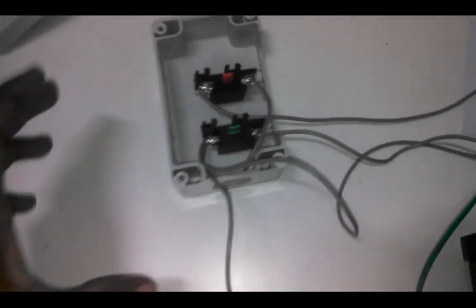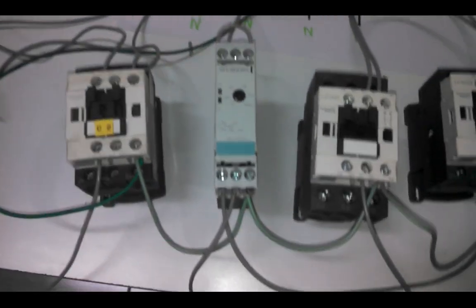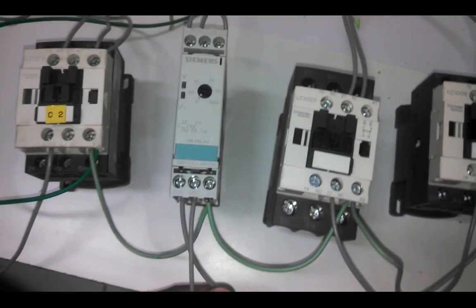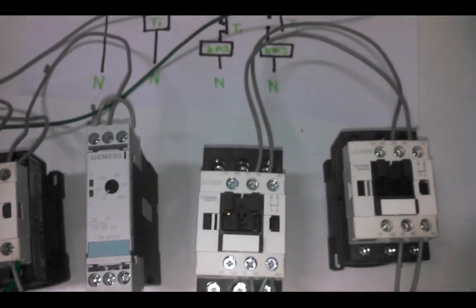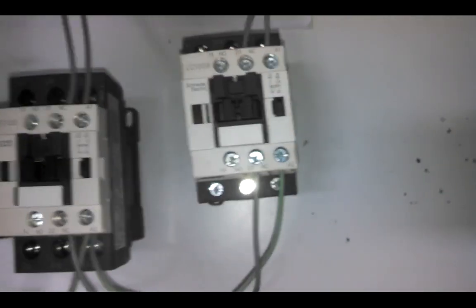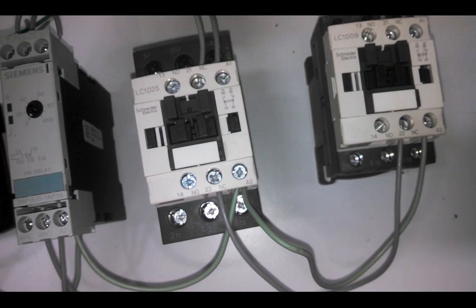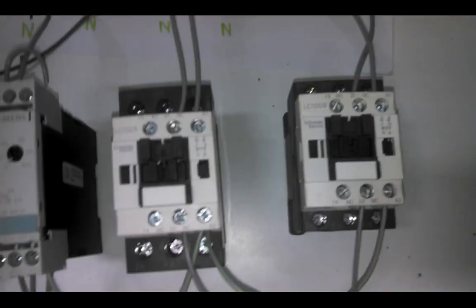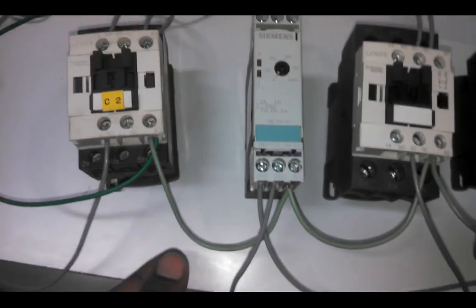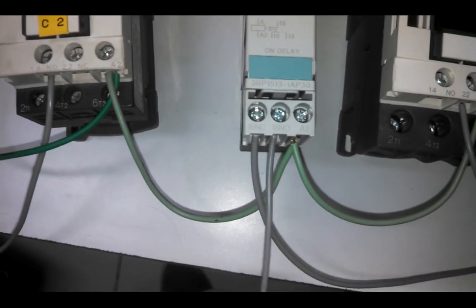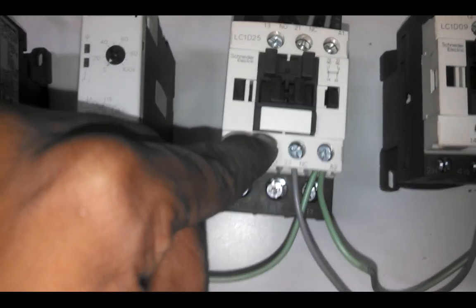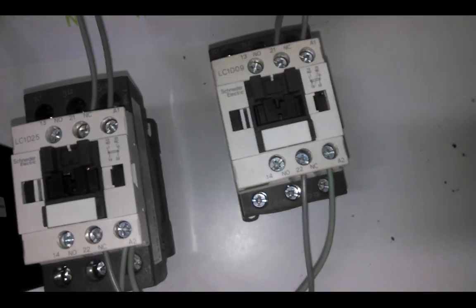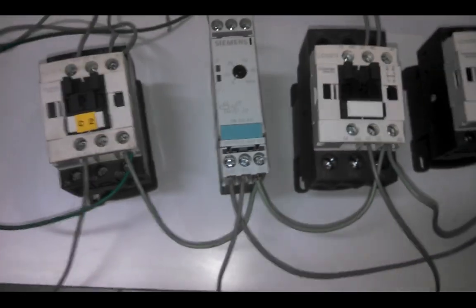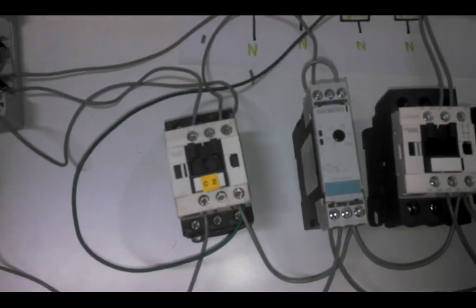So the wiring has now been done. As you can see, this portion will be our DOL starter, and then here comes the wiring for the star delta starter. The 16th terminal will pass through this NC contact, and then this came on the coil supply of this star contactor. Green is taken as neutral in the whole circuit, and when the 5 seconds have been completed, the supply would come on the 18th terminal on this wire, and this will pass through the delta contactor NC terminal, and this will hold the delta contactor. So let's test the starter and see how it works.